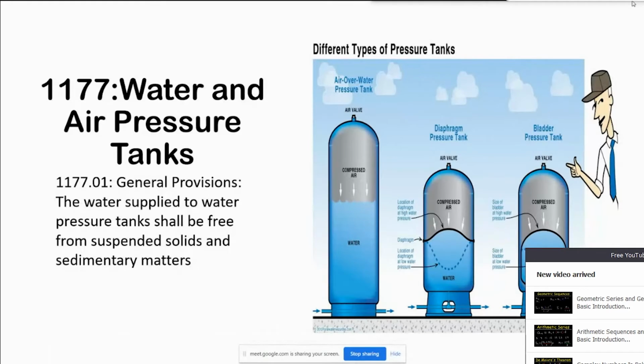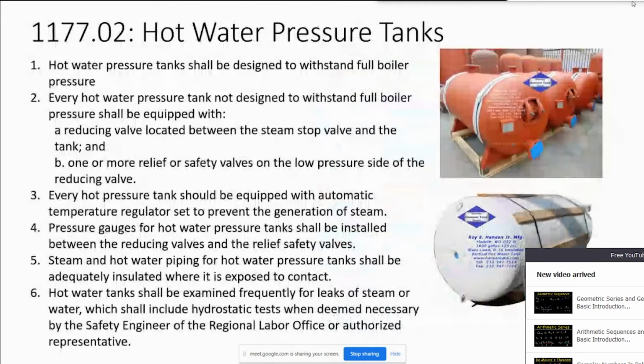Water and air pressure tanks. General provision. The water supply to the water pressure tank shall be free from suspended solids and sedimentary matters. Hot water pressure tank. Hot water pressure tanks shall be designed to withstand full boiler pressure. Every hot water pressure tank not designed to withstand full boiler pressure shall be equipped with a reducing valve located between the steam stop valve and the tank, and one or more relief or safety valves on the low pressure side of the reducing valve.